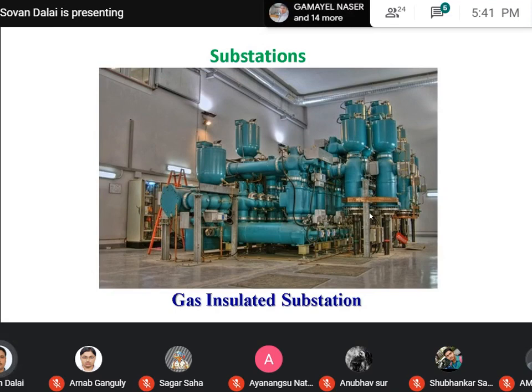because all the instruments, including the transformer, current transformer, potential transformer, circuit breaker, isolator, whatever components are present inside the substation, are all present inside this closed chamber, where instead of air, some gas acts as an insulator. In most cases this gas is SF6, sulfur hexafluoride gas, used as an insulator. So this is one of the advantages where the space is limited, where space is not available for an air insulated substation. So nowadays people are going for gas insulated substations. Now CSC also has some gas insulated substations in Kolkata.